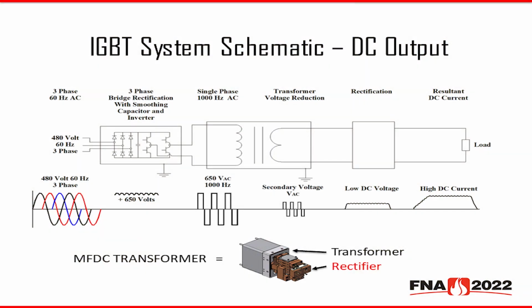So how does an IGBT MFDC power supply work? Here's a pictorial schematic of the process. If we start on the left side, the input into the system is 480 volts at 60 hertz, 3-phase. Other main voltages can be used. We just show 480 volts here. Within the IGBT control, SCRs then rectify the 3-phase up front to a 650 volt DC bus.